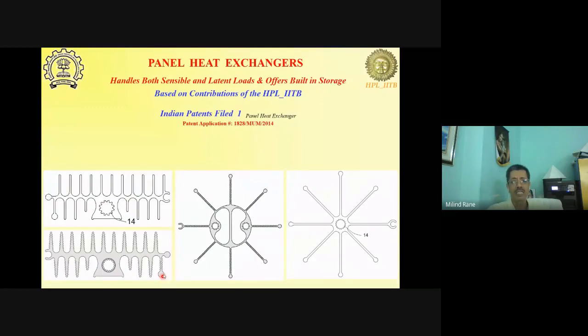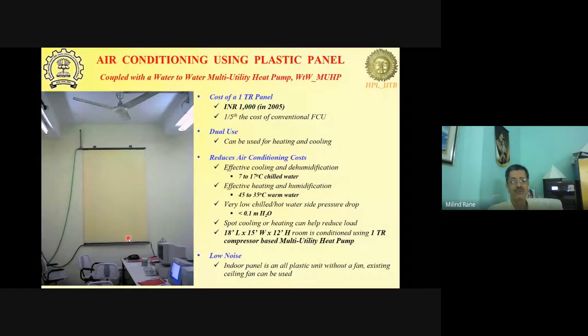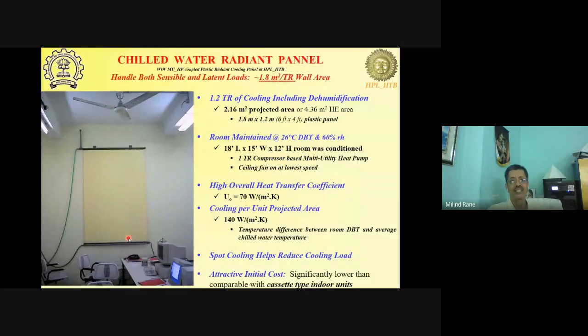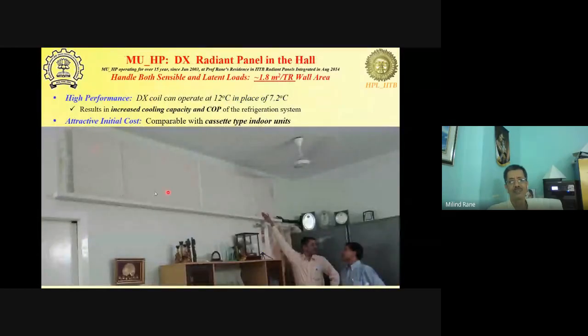So we can pass refrigerant or chilled water through these, and then this entire aluminum extrusion panel gets heated or cooled, and then it can radiate to or exchange heat with the surrounding air. So we have deployed cooling and dehumidification panels with plastic. This is the unit I talked about, my multi-utility 4-in-1 heat pump in my house. I have been using it since 2003. This is the radiant panel, based on a patented panel heat exchanger, where this cools and dehumidifies the air, and the ceiling fan is able to transfer the heat.